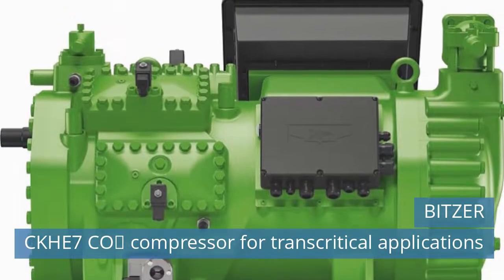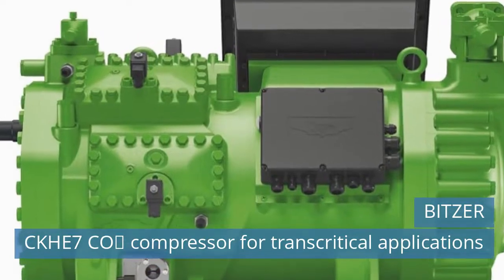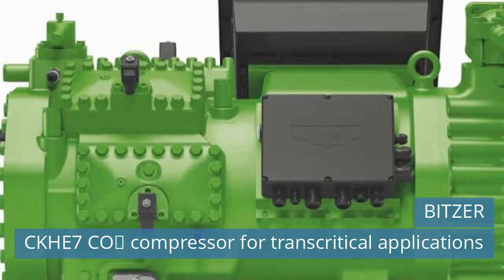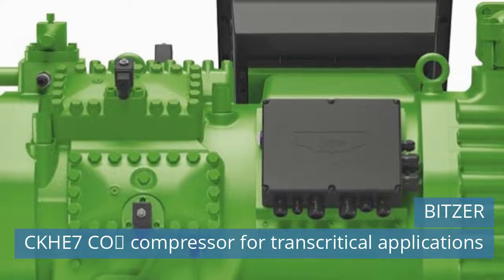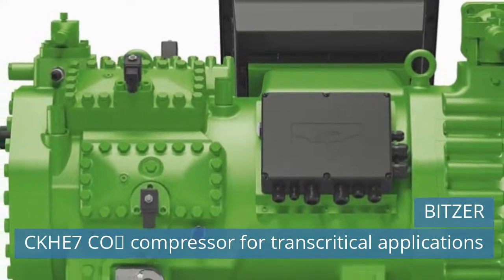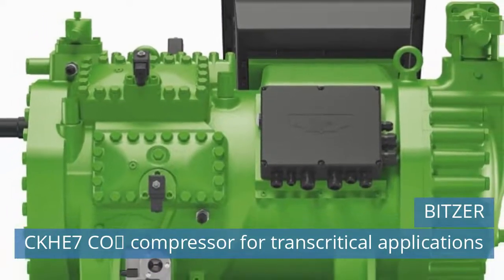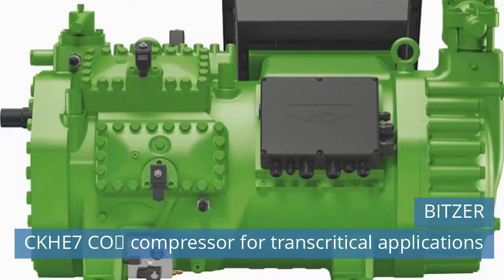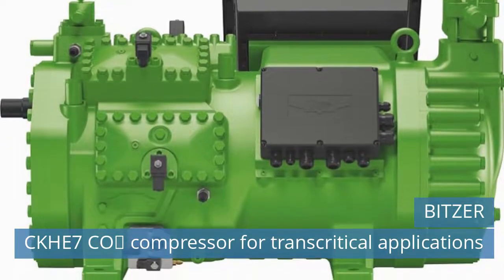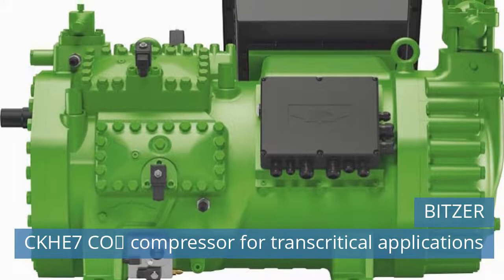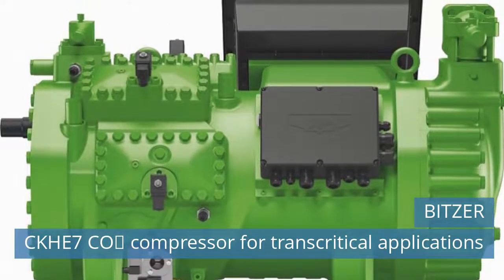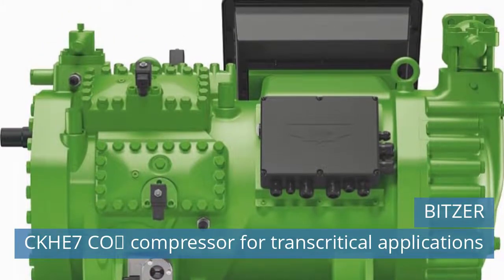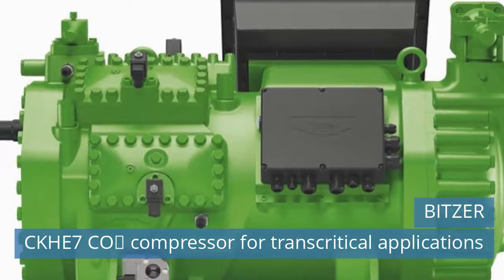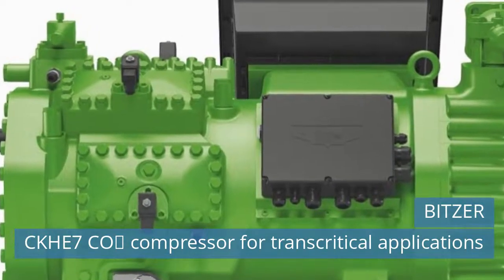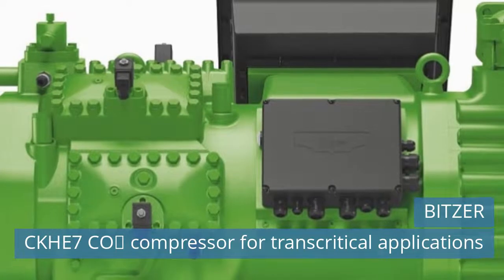Market trends show an increasing demand for industrial refrigeration plants with higher refrigeration capacities and the capability to use CO2 as refrigerant. Up to now, projects with required cooling capacities of more than 5 MW had to be divided into several individual systems. To meet the trend for bigger capacities, BITZER developed its new 8-cylinder CO2 compressor CKHE7 with displacement rates between 69.4 and 99.2 cubic meters per hour.